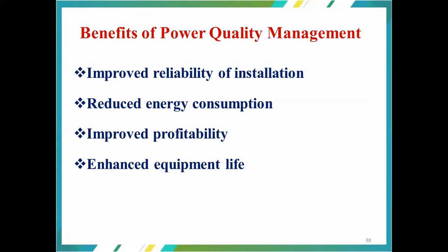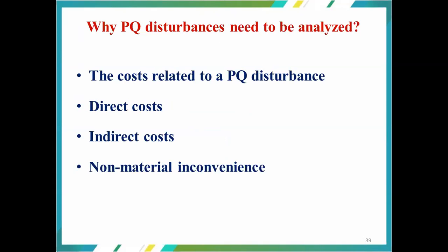And the benefits of power quality management is that, whatever it may be, either it's a drive load, or a charging station, or a direct charging of the batteries, etc., there's improvement. The benefits of power quality management are improved reliability of the installation as well as the reliability of the equipment. And the next one is reduced energy consumption. That means if you are reducing the kVA requirement, or you are maintaining the PF at a higher level, the losses are going to be reduced. The energy consumption is going to get reduced, and losses are also going to be reduced, and thereby you are going to increase profitability. And if the power quality is maintained in an expected manner, the life of the equipment is also going to be enhanced.